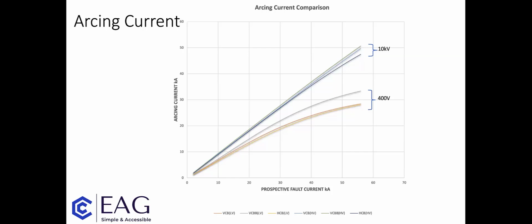So as you can see at 400 volts there again on the graph, that difference between the fault current and the arcing current can be quite marked. If we're looking at 50,000 amps prospective short circuit current, the actual arcing current could be as low as about 26,000 amps. And if your protection doesn't see that as a short circuit or just sees it as an overload, that's when you can get to extreme amounts of damage.